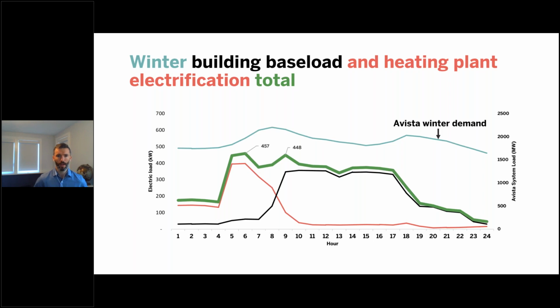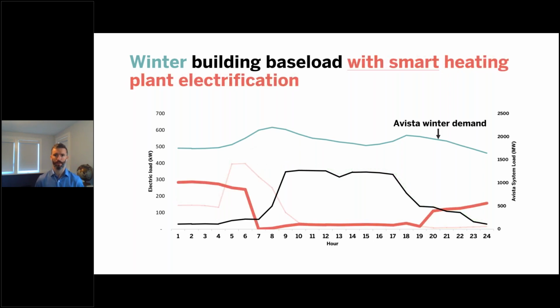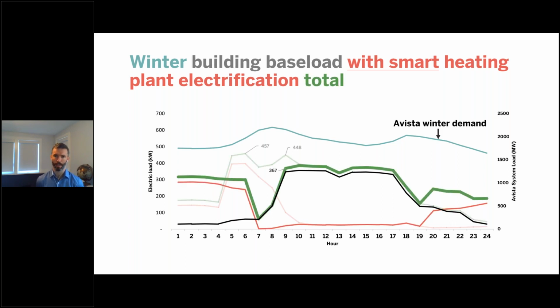If we move to the next slide, our central plant has approximately 24,000 gallons of thermal storage, which was designed and is dispatched to maximize heat recovery, particularly during shoulder seasons. But we also have the opportunity to utilize this asset to mitigate utility demands. Here, what I've done is simulated us shifting the original load profile, which is grayed back now in the light red, to show what we can do if we preheat overnight and store and dispatch that during the peak period, shown with the heavy red curve. And if we move to the next slide, in this way, and with the green curve showing the sum of those loads, you can see how we have the potential to deploy in-building assets for utility benefit and to move outside of the utility peak. Here we reduce our peak demand during the morning peak by 20%, but our average demand during that morning peak is reduced by over half.